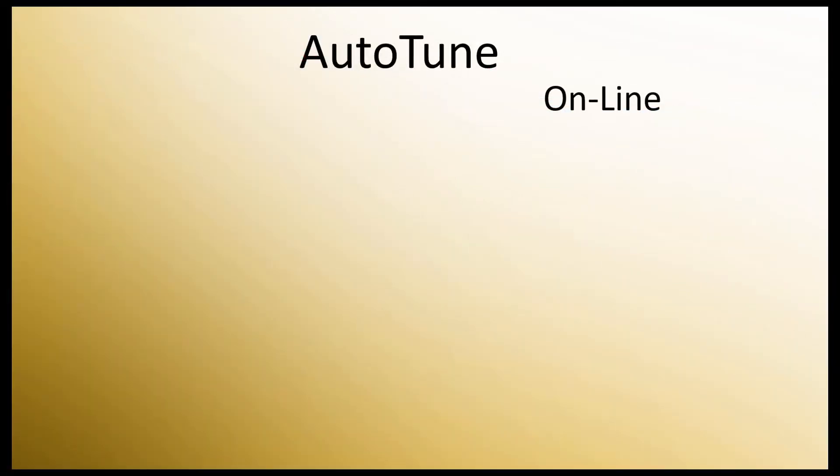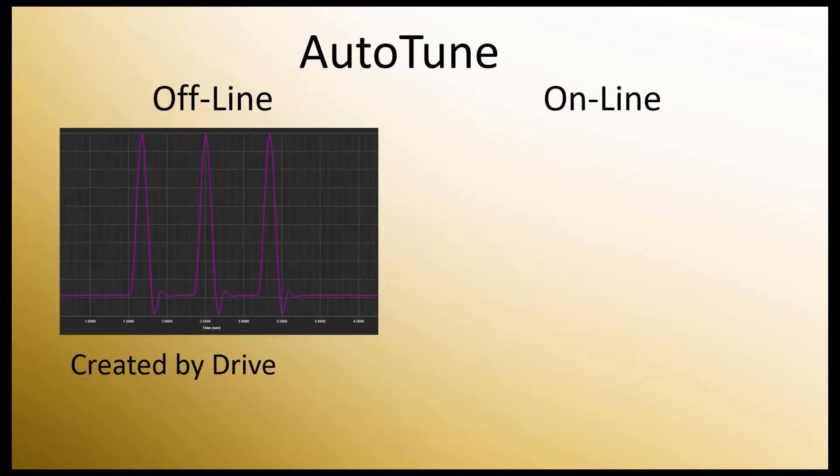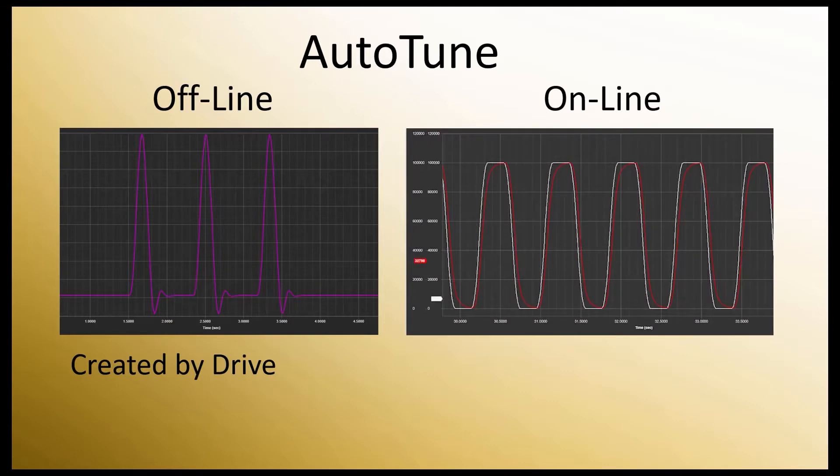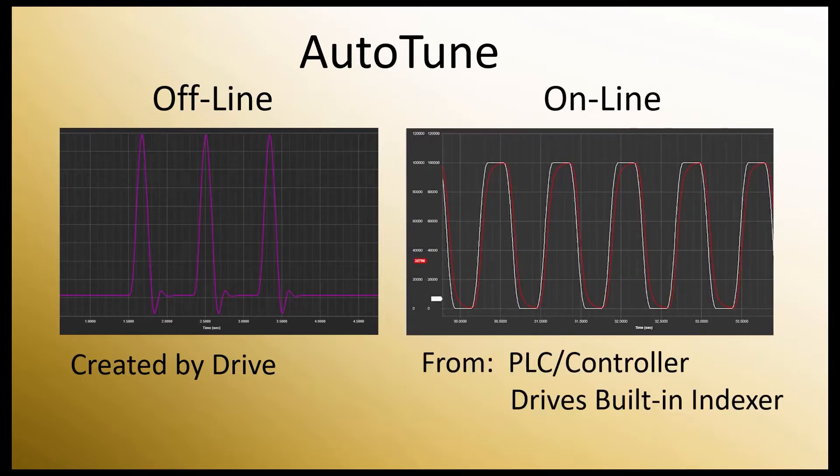Online tuning is similar to the offline tuning we did in the previous video. The difference is, instead of issuing 3 pulses to do the tuning, it tunes the servo system to whatever waveform is supplied by an external PLC controller or the servo's internal indexer while the system is running.